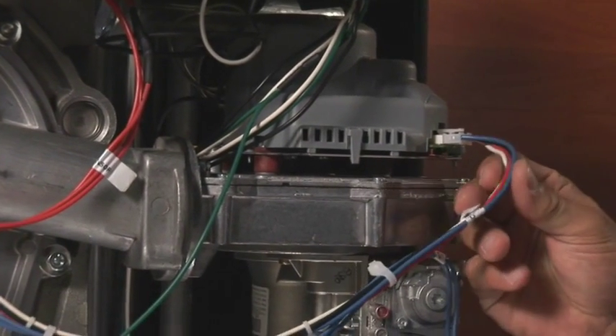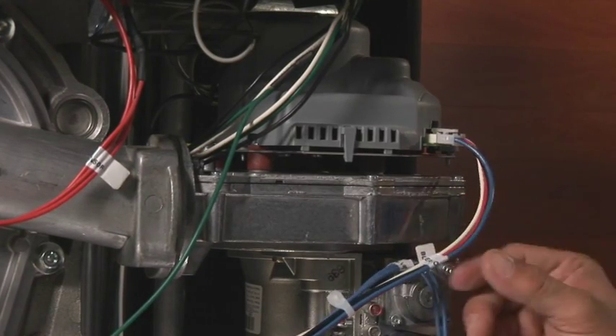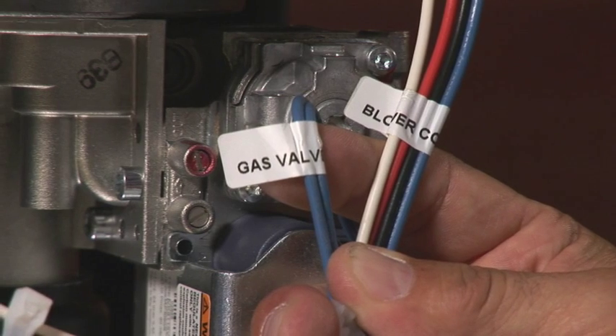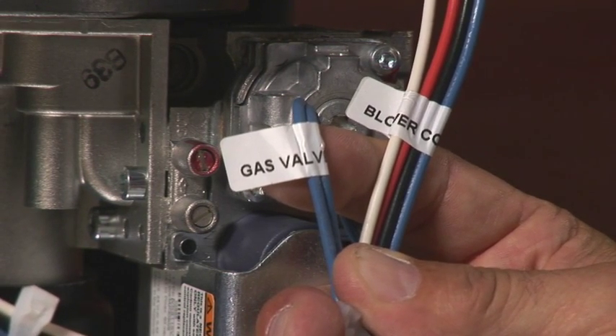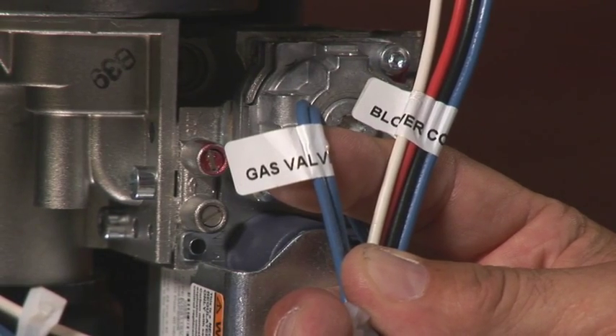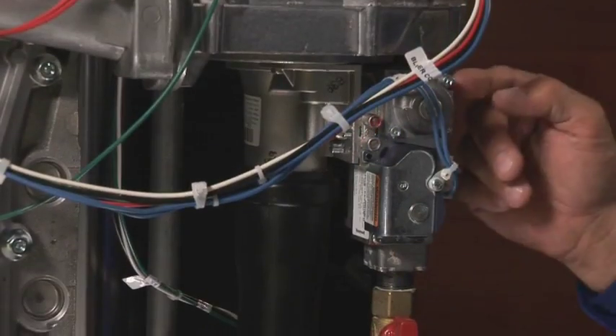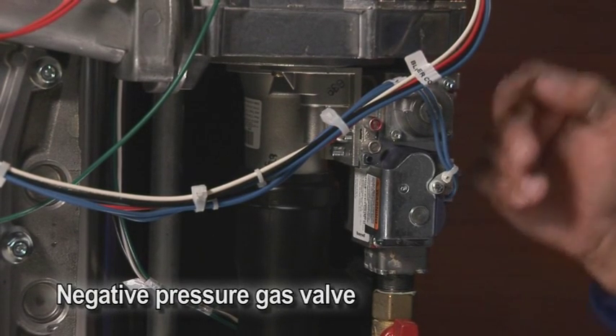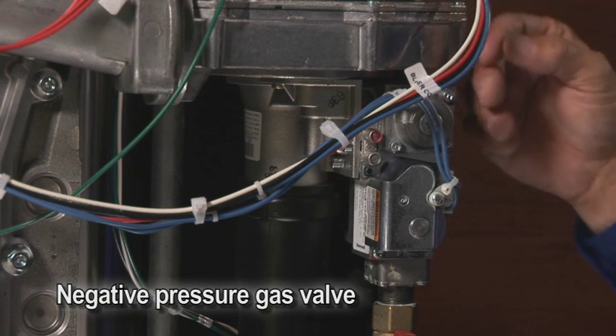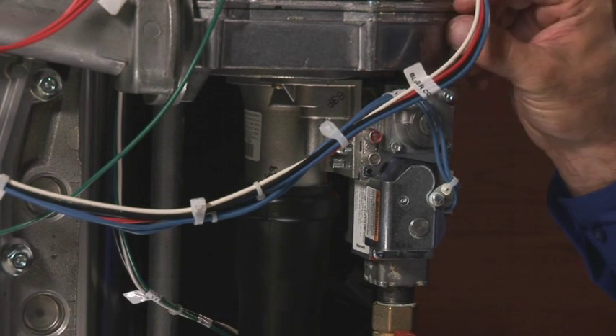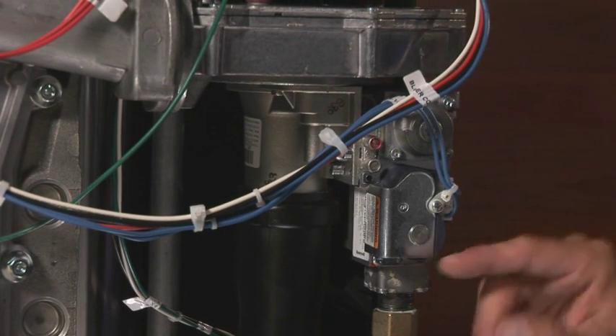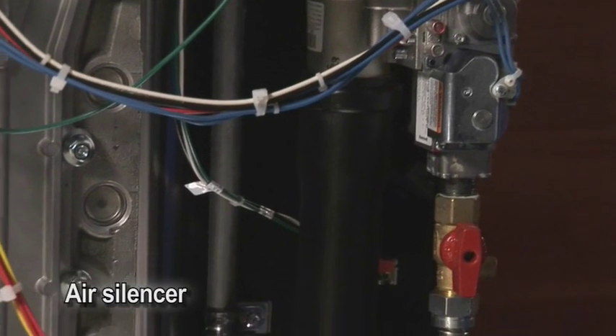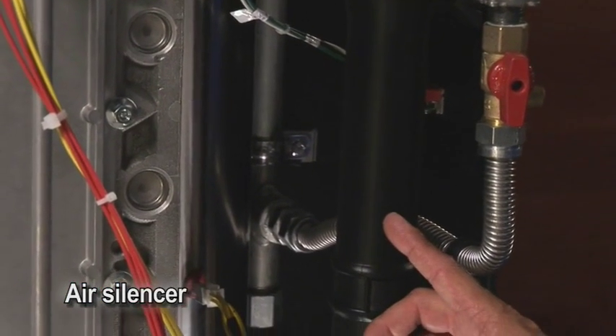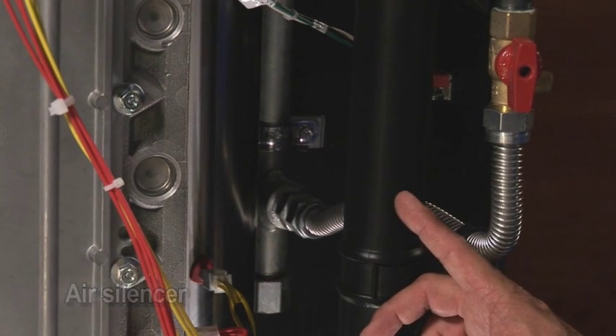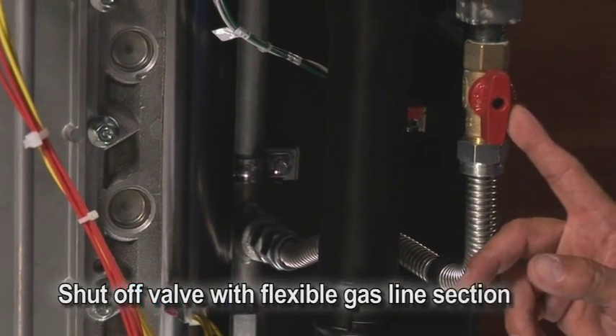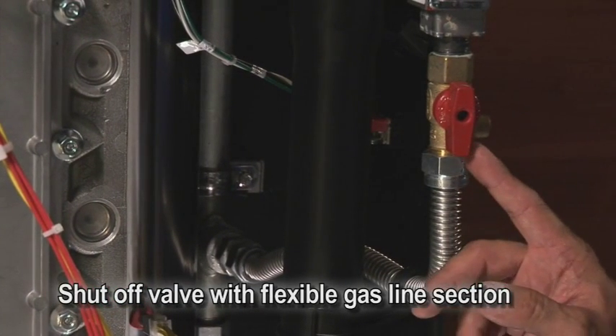This is the signal cable coming from the control down to communicate with the blower motor. As you can see here, all of the cables are marked with the specific function that they do. From blower signal to gas valve, everything is marked. This is a negative pressure gas valve. Based on the revolutions of the blower motor, gas-air mixture is drawn through, mixed, and then injected into the burner. This is a silencer tube. This draws the air from the compartment up through the venturi into the combustion blower and injects it into the burner. We have a shutoff valve on the gas line with a flexible connector on all the boilers.